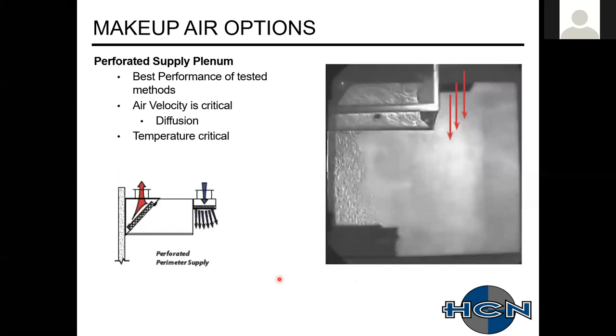Next option, and one that's currently used by most manufacturers now, is a perforated supply plenum or a plenum box in front of the hood. Out of all the tests, this one showed the best performance. With all the integrated makeup air approaches with hoods, the biggest thing is having the proper velocity and also having the proper temperatures. Warm air tends to rise, cooler air tends to fall. So if you have ice cold air coming out from a front plenum like this, you can definitely see it coming down. I've seen pictures of makeup air plenums where they're using untempered air up in the north, and this is all frozen out.